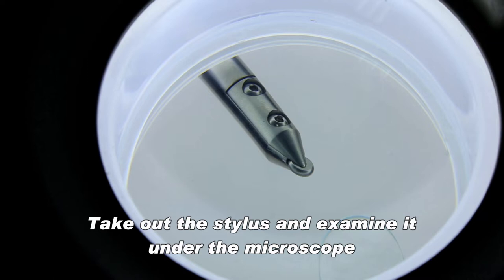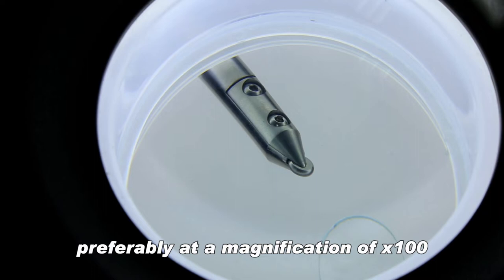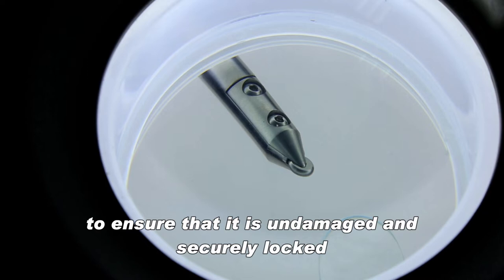Stylus inspection: Take out the stylus and examine it under the microscope, preferably at a magnification of X100, to ensure that it is undamaged and securely locked.